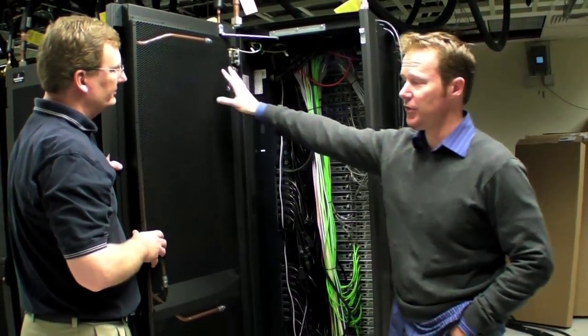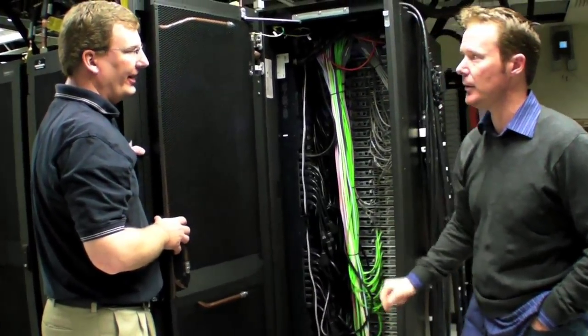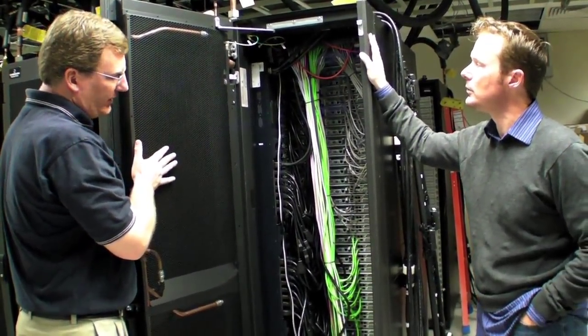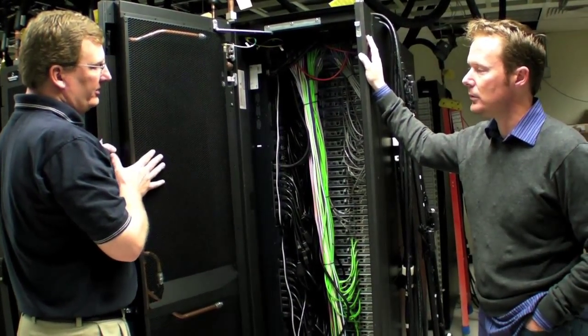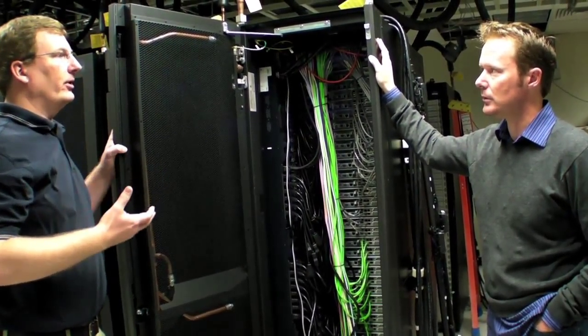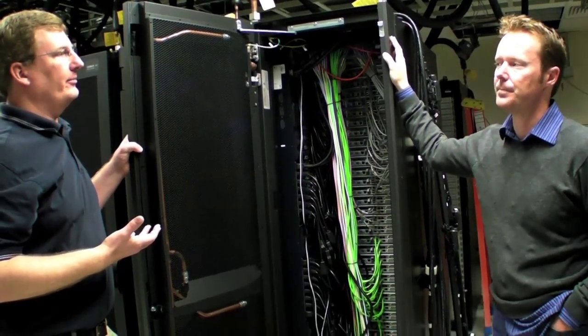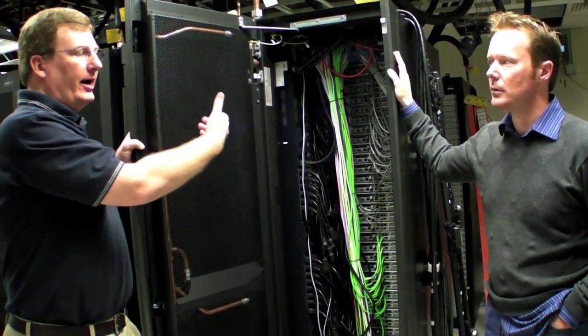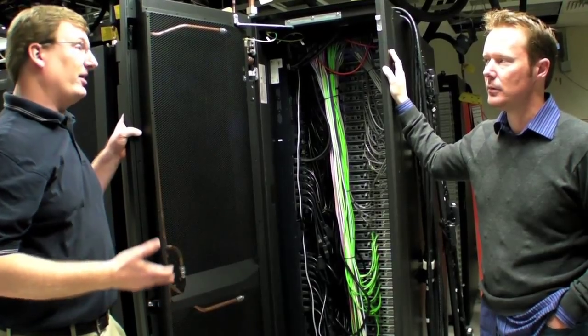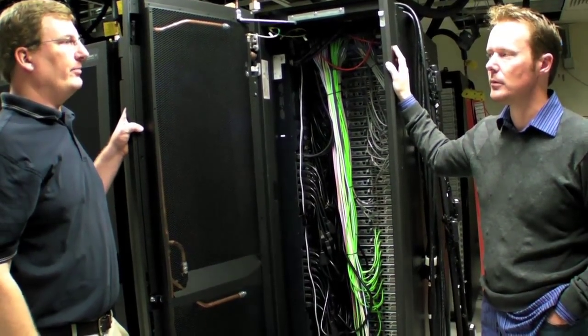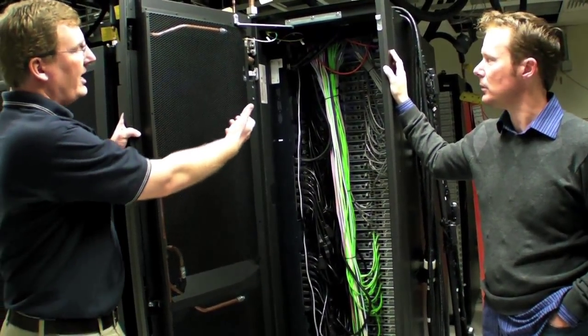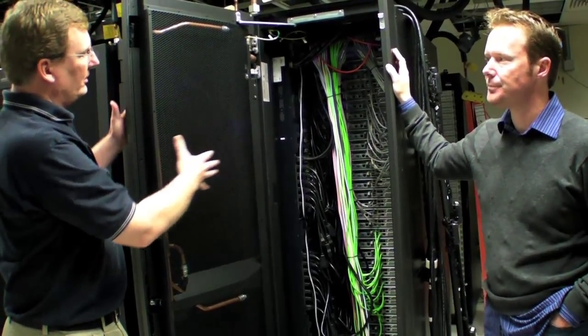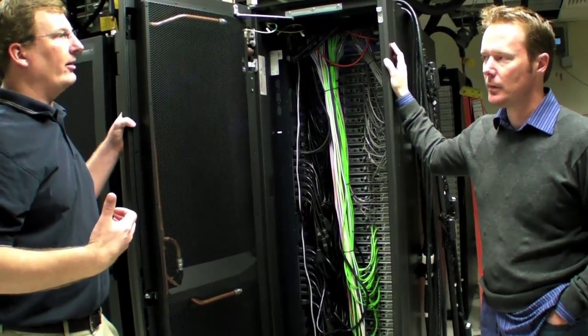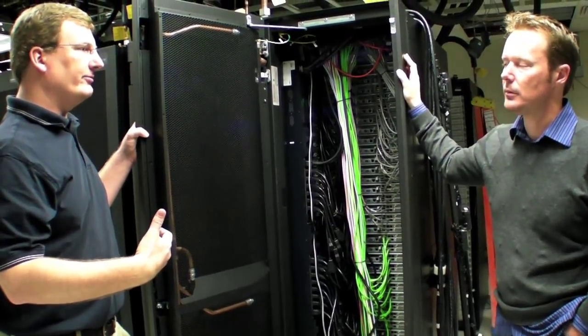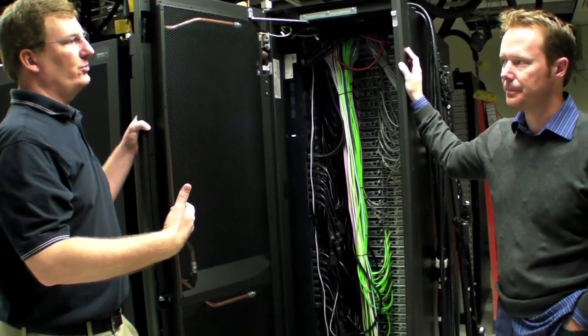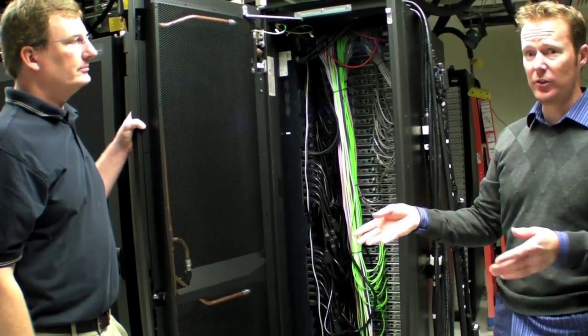So the entire heat exchanger is built into this rear door. It's a 20 kilowatt capacity, and the way we designed this was to create a room-neutral environment. What that means is if you have a data center typically around 72 degrees Fahrenheit, air comes into the servers, heats up, but then goes through this rear door before going back out into the environment. And when it comes back out, it's at that same temperature as when it came in.